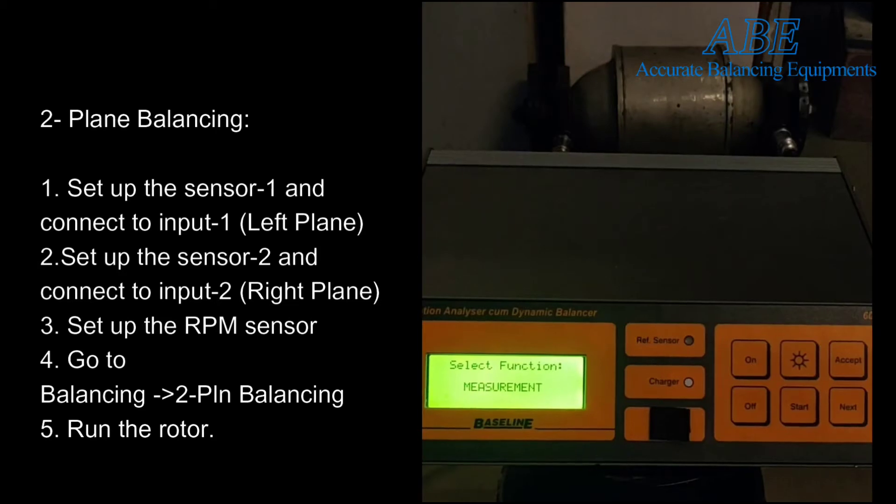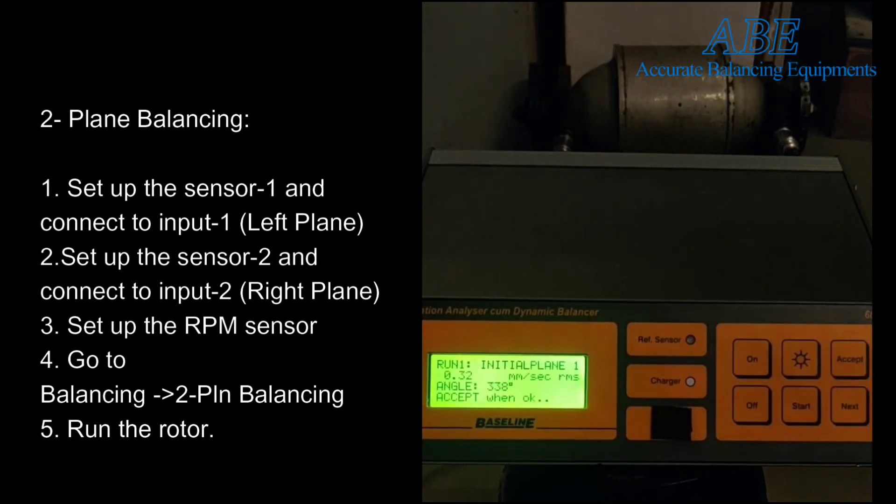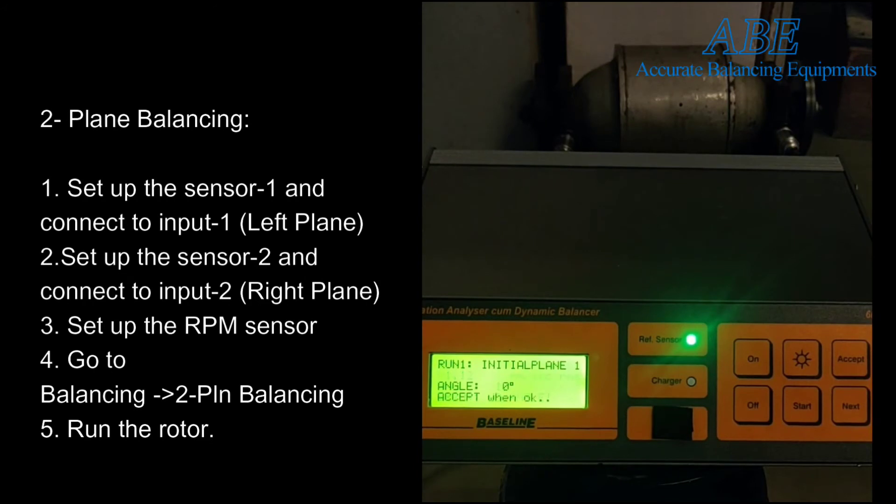Here is a demo of two-plane balancing using the 6050. Connect one sensor to input 1, left plane, and the other to input 2, right plane. Make appropriate instrument settings in balancing setup. Connect the reference sensor, then go to balancing and select two-plane balancing.